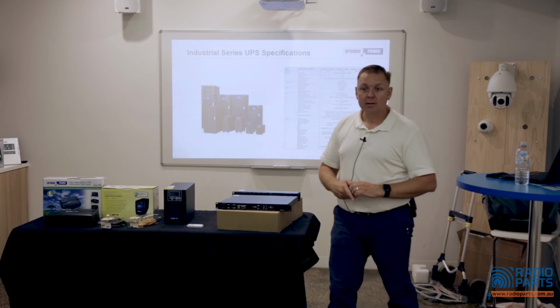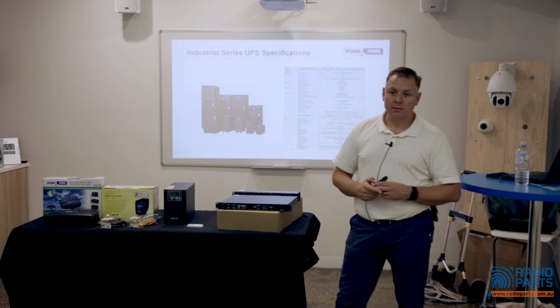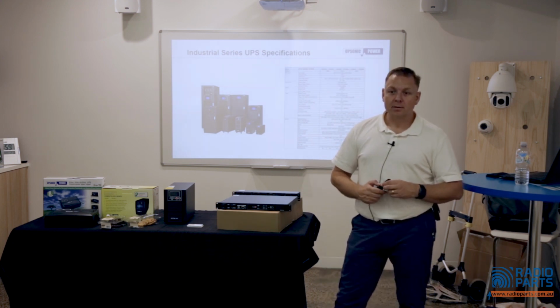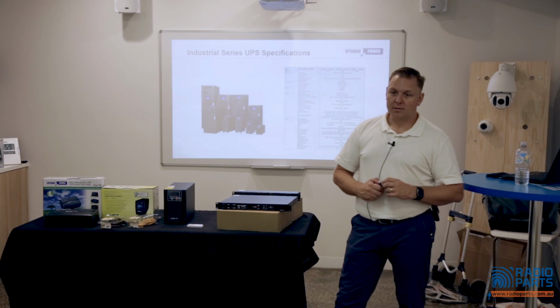I had a customer inquire once on an interesting subject - they were powering a horticultural unit in the backyard, and wanted to know if they could set series timing on it, so they could make timing series for the whole horticultural setup: run for 7 hours at this time, from here to here, then stop. They wanted to know if there was a safe or good way of having the UPS handle that without issues from the constant powering on and off.